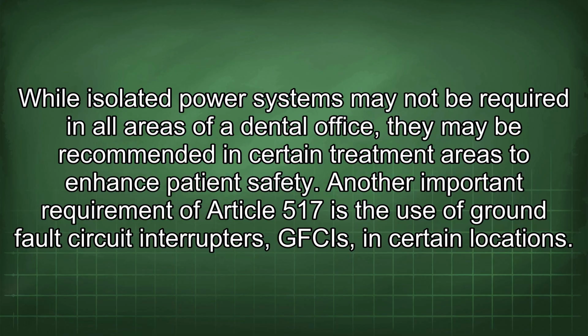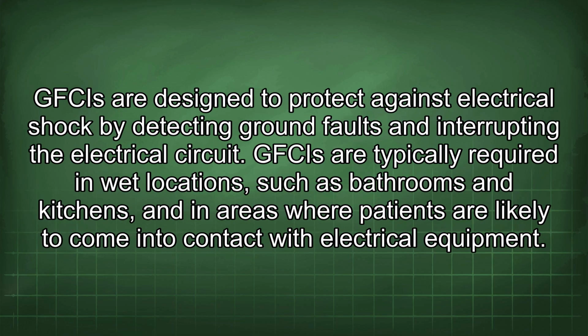Another important requirement of Article 517 is the use of ground fault circuit interrupters, GFCIs, in certain locations. GFCIs are designed to protect against electrical shock by detecting ground faults and interrupting the electrical circuit. They are typically required in wet locations, such as bathrooms and kitchens, and in areas where patients are likely to come into contact with electrical equipment.